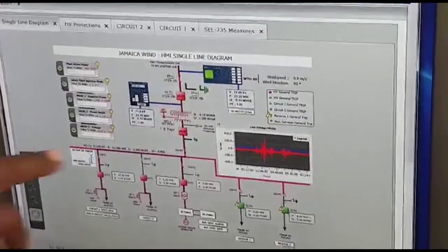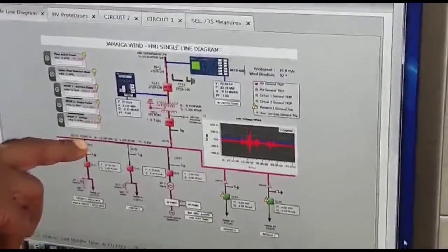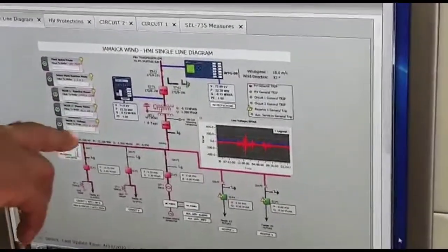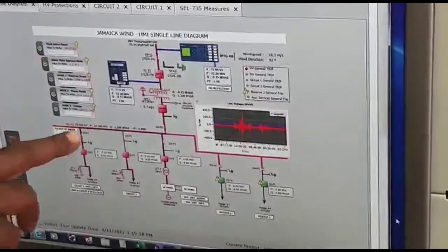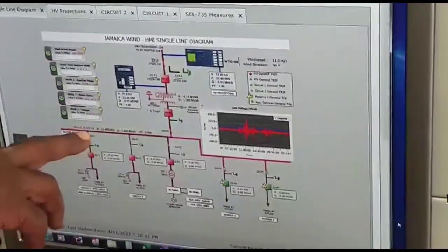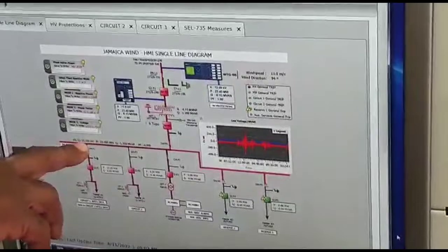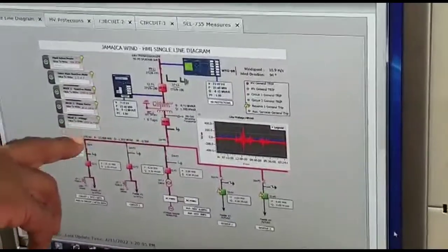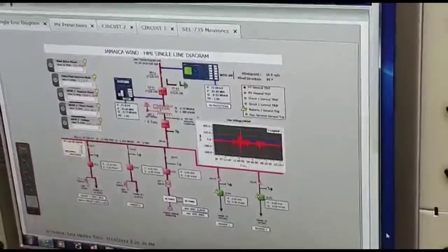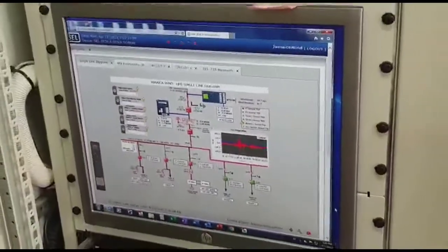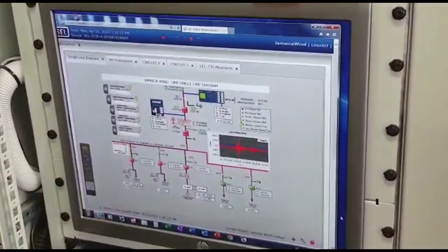So right now we need to put the tap changer in local and bring this tap down so that this 35.5 kV can go down to 34.5 kV, or as close as possible to 34.5 kV, which is right here. You get that figure right here?